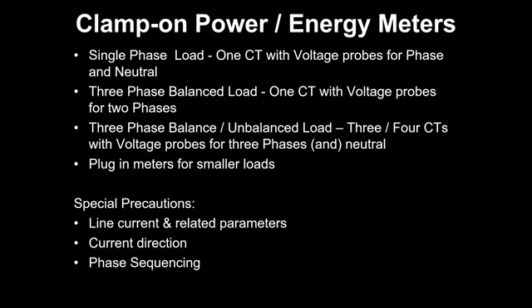The third is the three-phase unbalanced load meter. Like even for a balance load, you can do the measurements with it. The load is big, HT motors and all. When we are doing an audit, we use this third meter. It will have 3 or 4 CTs depending on the meter you buy. Four CTs will be expensive. It will measure the current in the neutral also. Otherwise, it will assume that neutral is 0 and it will measure three-phase voltages, three-phase currents, and based on that, it will do the measurement.